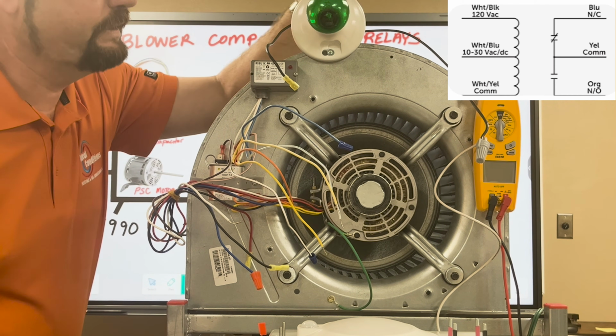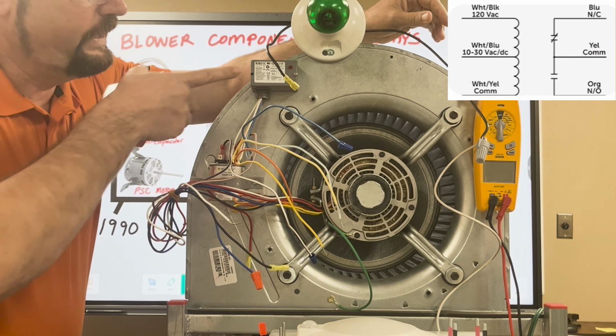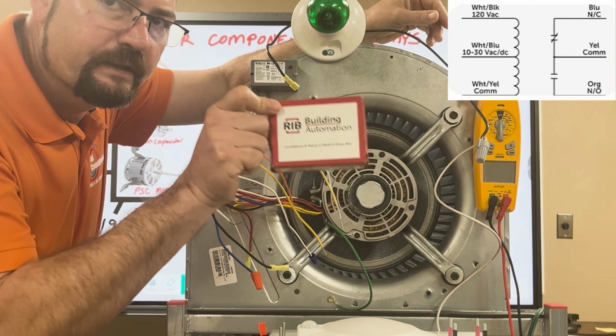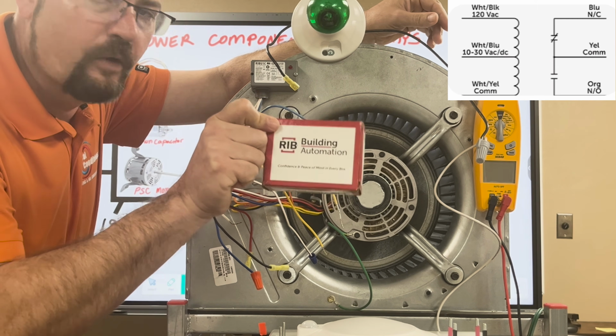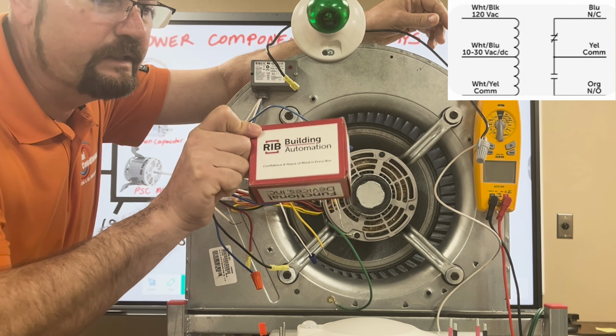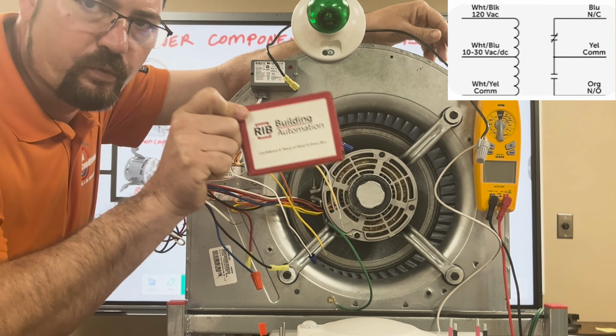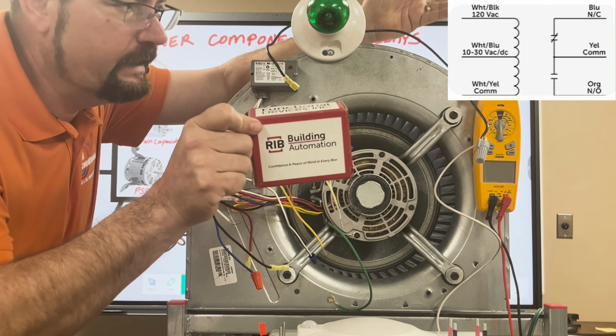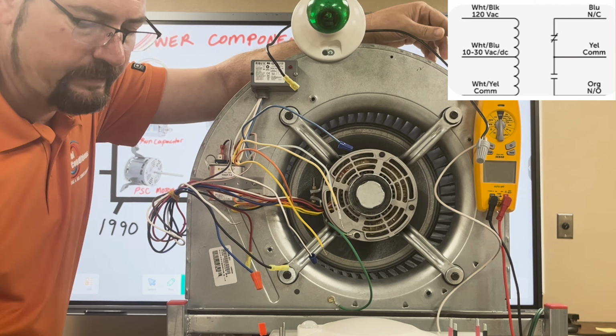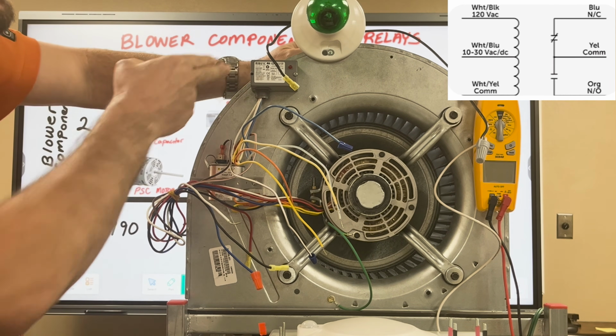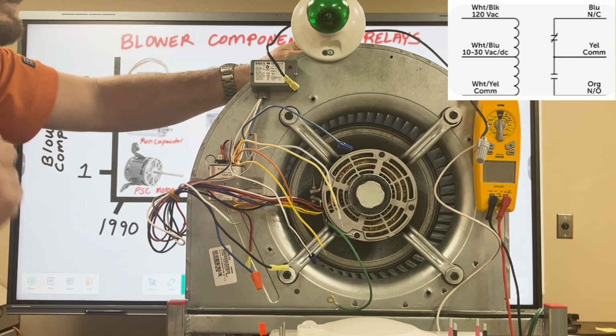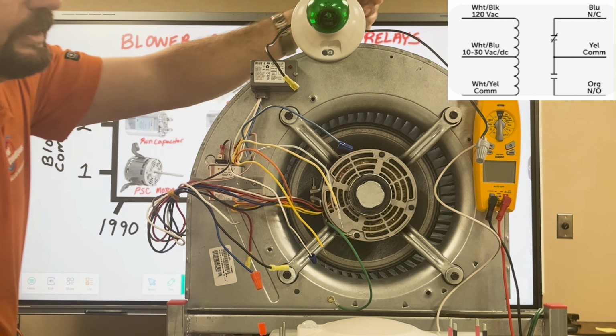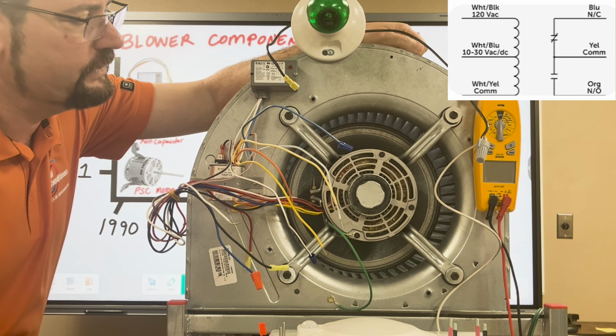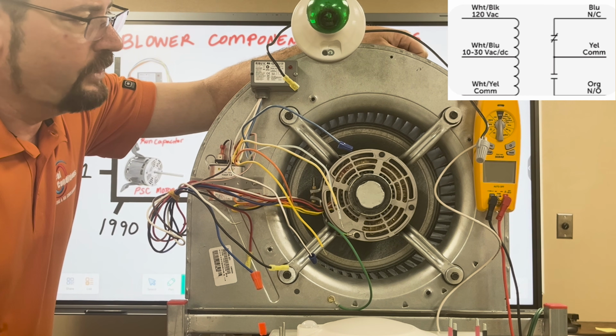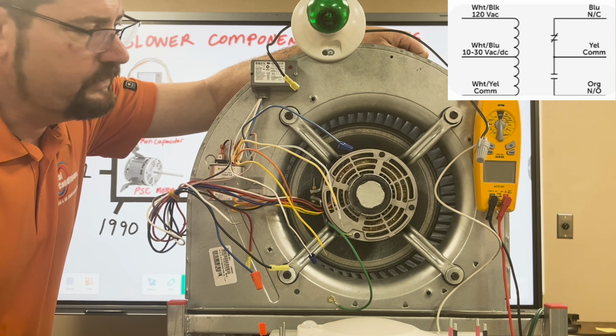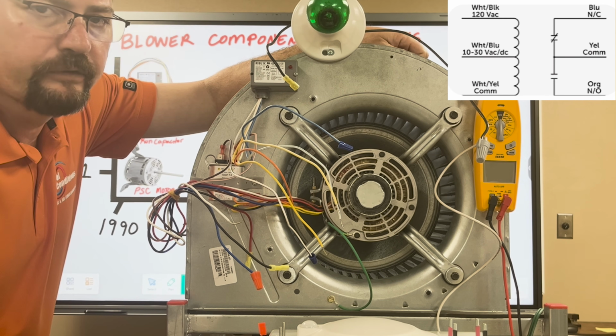The fan motor has a green light bulb this time. We have a RIB relay. I'm going to show you that this is always in a red box. This is how they brand it, RIB, which stands for relay in a box. At the end of it, you can use this for a blower motor, for a light bulb, pretty much anything on the building automation side. And it's always on the shelf, typically at your HVAC supply houses.